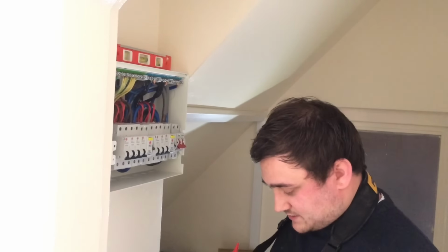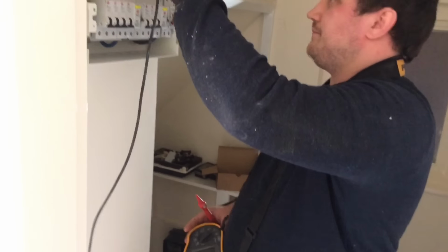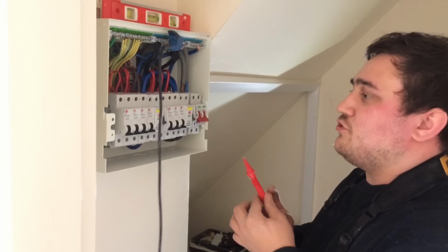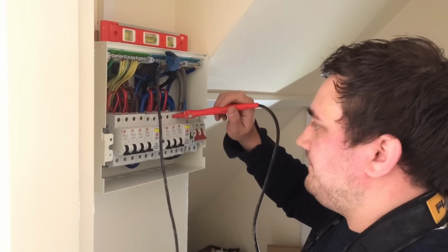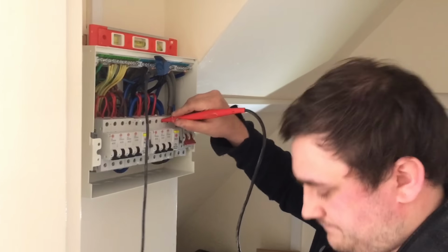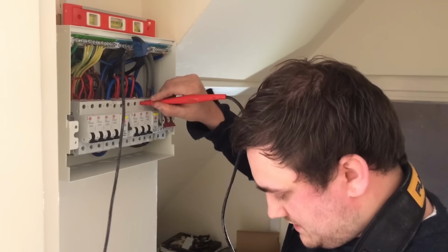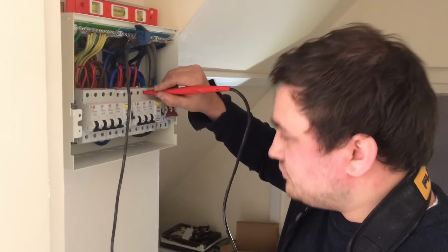So I've set my tester to 500 volts DC. I'm going to probe onto the neutral bar for this side of the RCD. And then on the top of the breakers, 500 mega ohms.